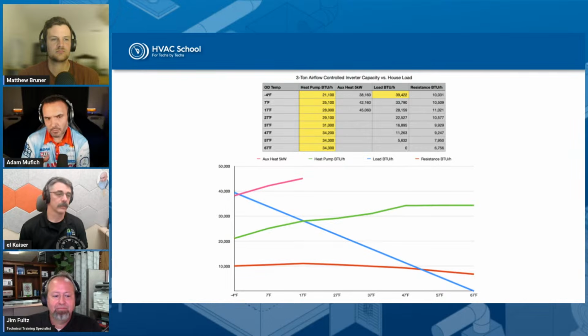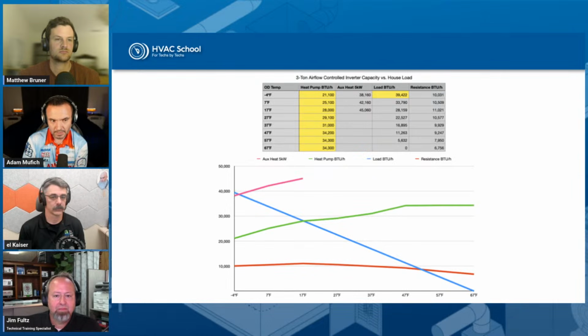I wanted to make one point on this, what you're saying here. Everyone needs to keep this in mind too when they're setting up these controls, because with the heat pump, we're talking about COP, coefficient of performance, and when you're over 1, it's more efficient to run than resistance, right? So that 28,000 that you just mentioned, that's cheaper. I don't want to say it's cheap, but it's cheaper heat, right? And then the 17,000 is expensive heat.